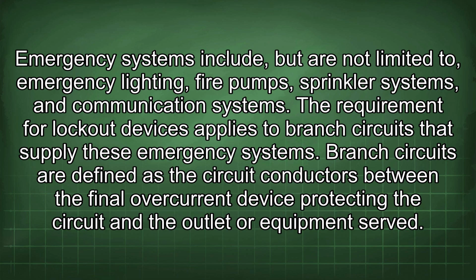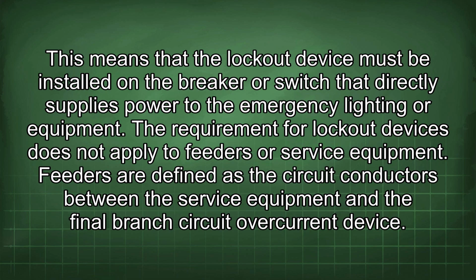The requirement for lockout devices applies to branch circuits that supply these emergency systems. Branch circuits are defined as the circuit conductors between the final overcurrent device protecting the circuit and the outlet or equipment served. This means that the lockout device must be installed on the breaker or switch that directly supplies power to the emergency lighting or equipment.